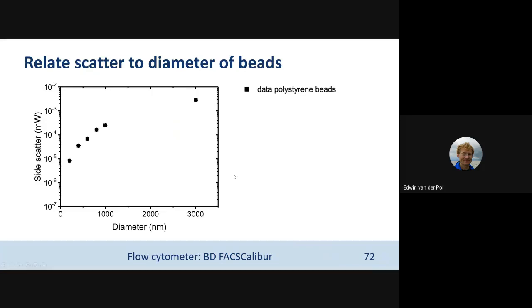We had no clue actually whether it was a possible approach, so we did the same in 2012. We bought some beads — beads are just plastic or polystyrene calibration particles that are spherical. We measured the side scattering intensity, calibrated the detectors, and made it in real power in milliwatts.